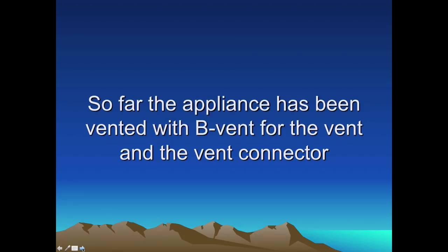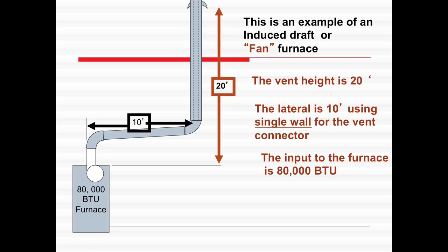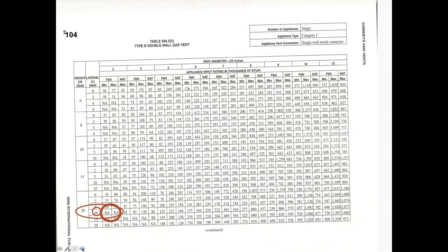So far, all we've done is use B vent for the vent and the vent connector. Let's change the vent connector to single wall with B vent for the vertical vent. This is an induced furnace, 80,000 BTUs, 10-foot lateral, 20-foot height. Onto the chart — now this is a different chart. Type B double wall gas vent, however over here it's a single appliance with a single wall metal connector. That's the difference.